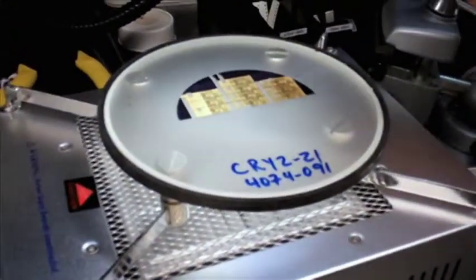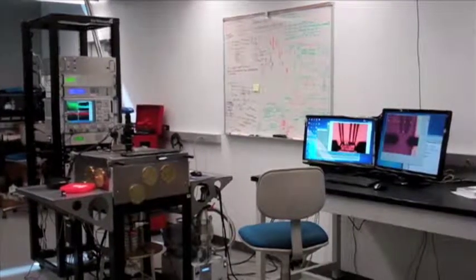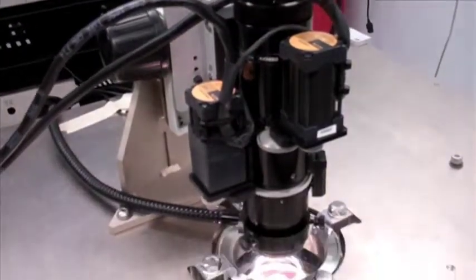It's actually smaller than the wafers we will be measuring in that probe station. And you can see there that there are many small repeating patterns, and each one of those is an individual circuit. It may be an amplifier or something else. The idea is we'll take one of these wafers and place it in the probe station, and then those pronged connections, we will land each one of those on one of those devices very carefully, because everything is very delicate.